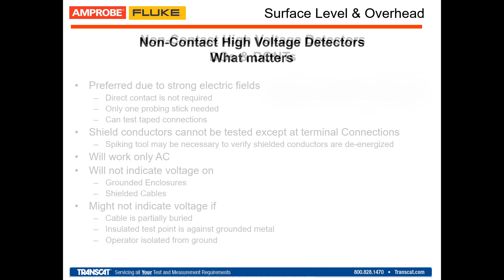There's another element that should be considered when you're purchasing an NCV, a non-contact voltage detector, and this ties back to safety, right? Safety standards, safety compliance, safety testing, safety certification. Some brands in the market offer detectors that have gone through intrinsic safety evaluations. We have seen in Europe some brands that comply with ATEX certification, intrinsic safety certification, but this guideline is not traceable to NFPA USA, or recognized by OSHA. And here in the States, I believe we haven't seen a non-contact voltage detector that is compliant with an intrinsically safe regulation, with the exception of the Amprobe TIC 300.